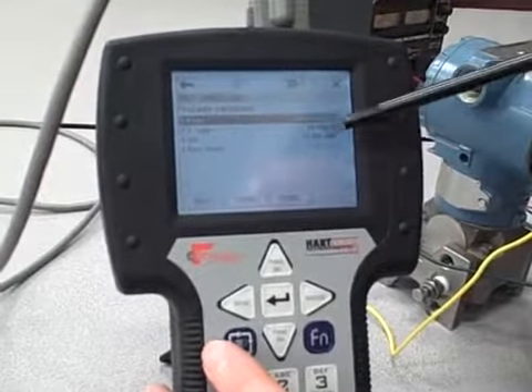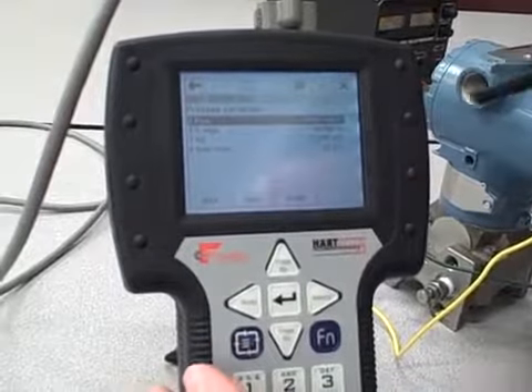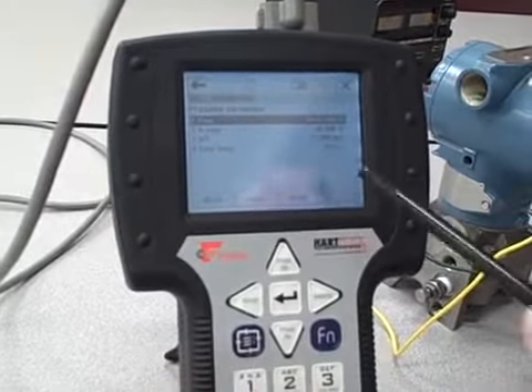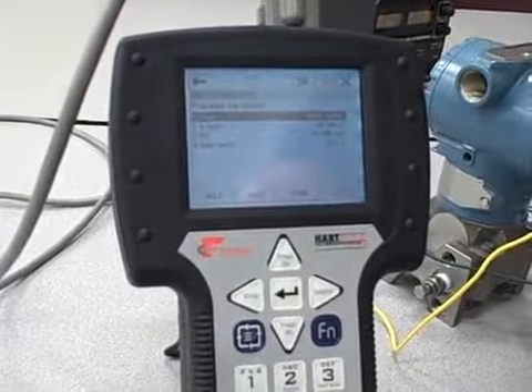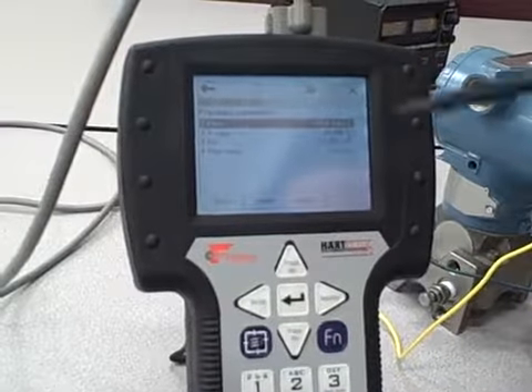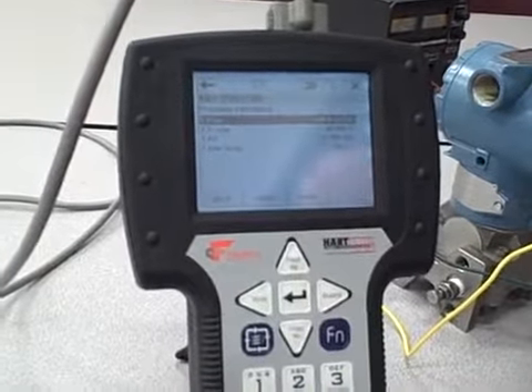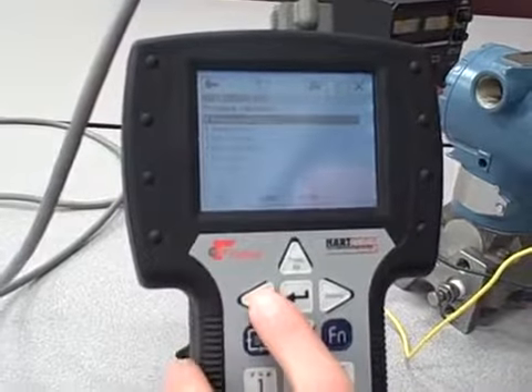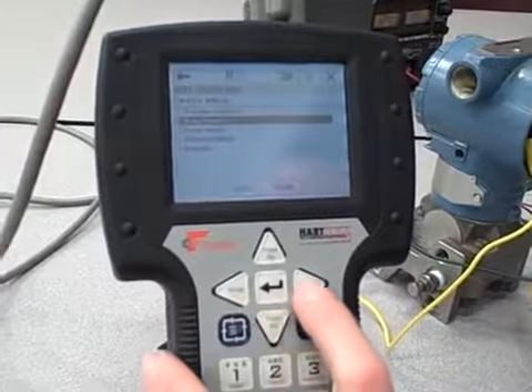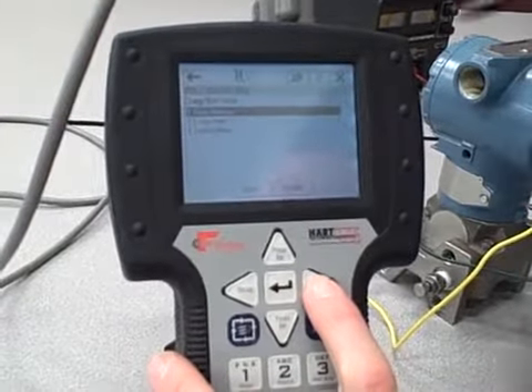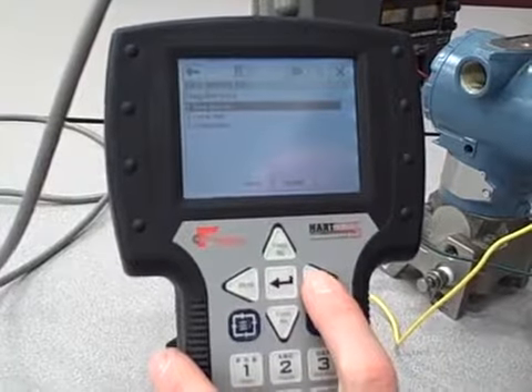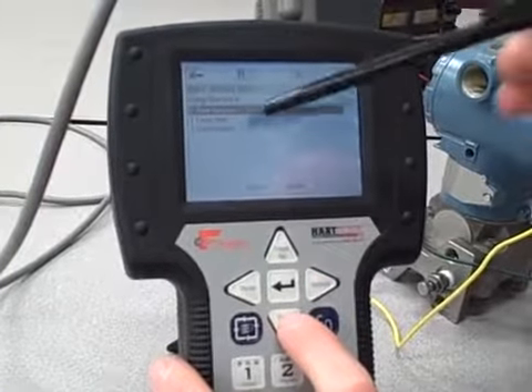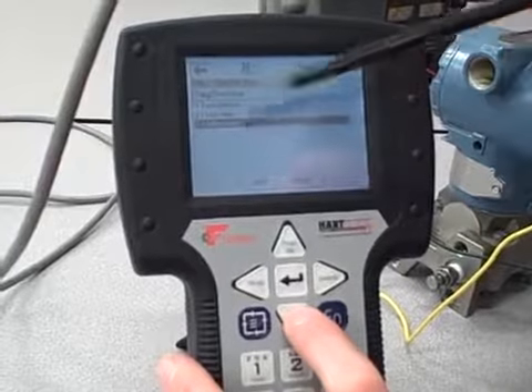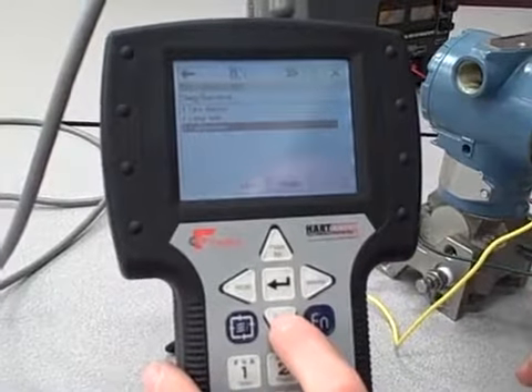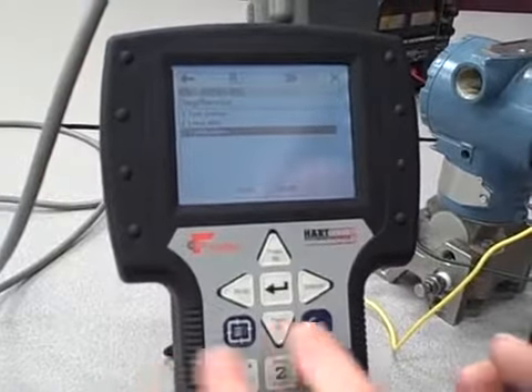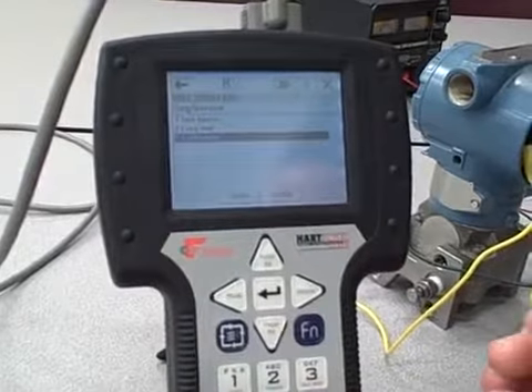Analog output about 11.998 or 12 milliamps. And sensor temperature, this is the ambient temperature of the differential pressure sensor. At room temperature here, about 22 degrees Celsius. I can go back, go into my next menu, diagnostic service. Here I can perform various self-tests. I can test the loop, and I can also go into calibration and actually do trim adjustments for both the sensor and the D to A converter for the 4 to 20 milliamp output.